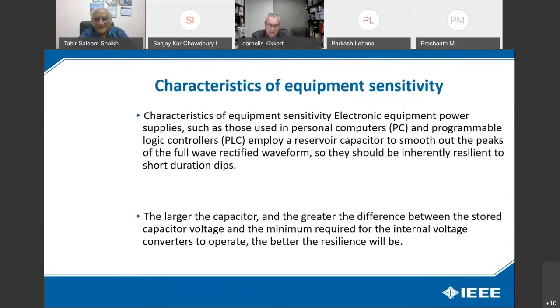Equipment sensitivity. A characteristic of equipment sensitivity is that electronic equipment power supplies, such as those used in personal computers and programmable logic controllers, PLC, employ a reservoir capacitor to smooth out the peaks of the full wave rectified waveform. So they should be inherently resilient to short duration dips. The larger the capacitor, the greater the difference between the stored capacitor voltage and the minimum required for the internal voltage converters to operate, and the better the resilience will be.